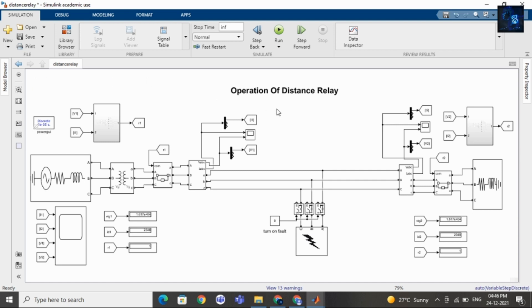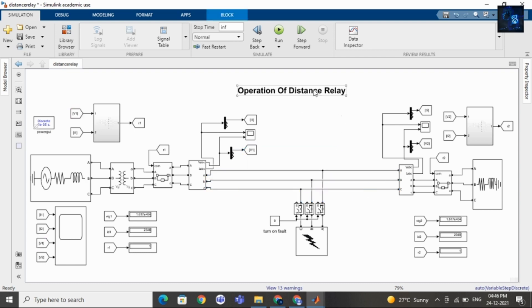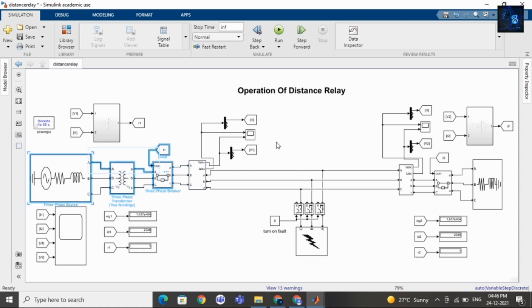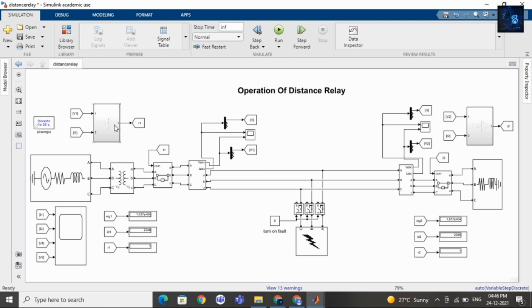Here you can see this is a three-phase transmission line. We all know that the distance relay is a type of protection relay most commonly used for transmission line protection. The distance relay will measure the impedance from the installation side to the fault location, and operates if there is any change in the measured ratio of voltage and current.